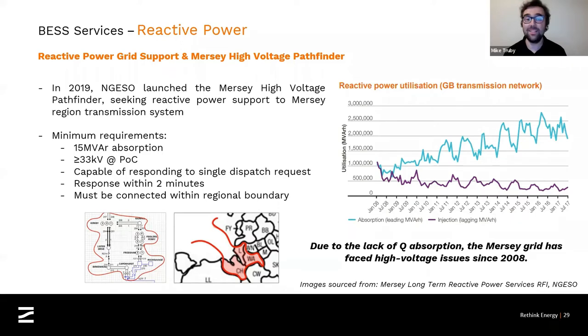The second thing to mention is that the voltage also matters. The higher the voltage at which you can take system actions with reactive power, the more impact those actions will make. The tender was open to connections at 33 kilovolts and above, but the higher the voltage you can connect at and do something about it, the more impact you can make. The final thing worth mentioning is that the response needs to be quick, because as voltage starts to become unstable, you need to be able to manage that quickly. Zenobē was successful in winning one of two contracts awarded as part of this reactive power service. It was the first battery, I believe, at least in Europe, if not the world, to win this service with National Grid.